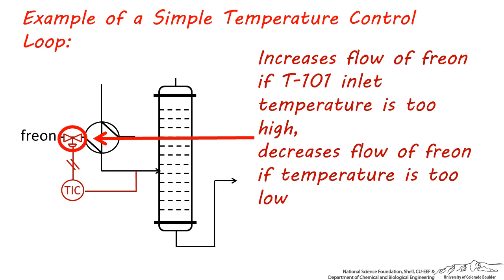Keep in mind that because of the size of this process and the high flow rate of the refrigerant in the process stream, so long as this process is in operation, freon will always be flowing through this heat exchanger. All the valve is doing most of the time is slightly modifying or regulating this flow based on the downstream temperature to ensure it remains in the specified range.